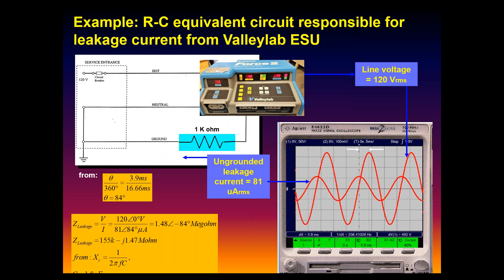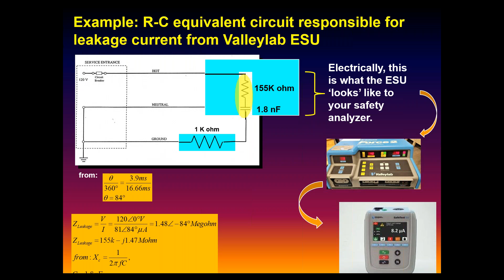...we have an equivalent capacitance of 1.8 nanofarads in series with a 155 kilo-ohm resistor. So from the perspective of your safety analyzer measuring leakage current on any device, this is what it looks like. In other words, your leakage current analyzer doesn't know it's looking at an ESU, a vacuum cleaner, or a pump. It doesn't see that - it's measuring the current, and that current is coming from an equivalent, in this case, combination of R and C. That's what's giving rise to that leakage current - ultimately the source of it is this equivalent circuit inside the machine.